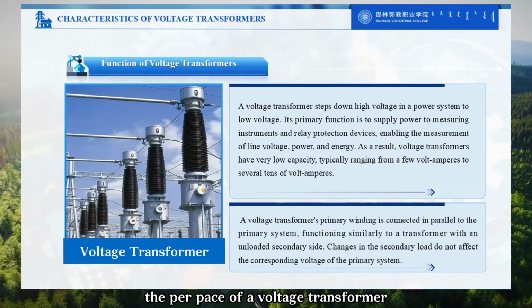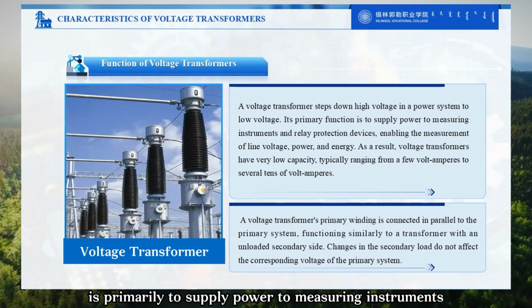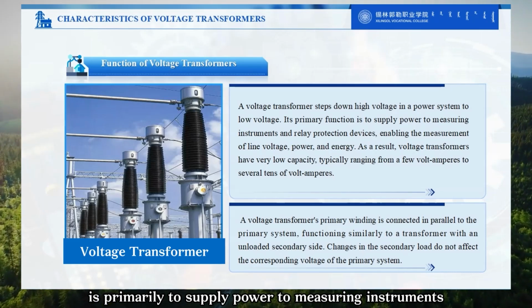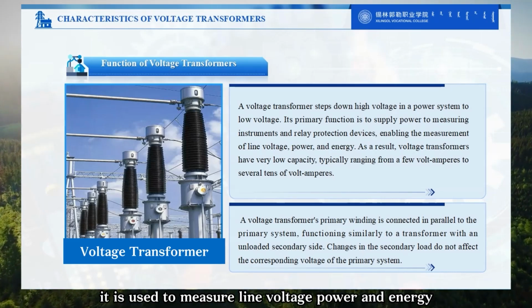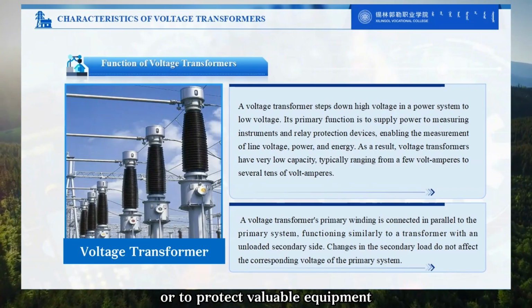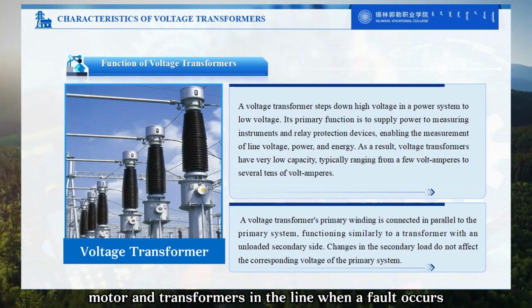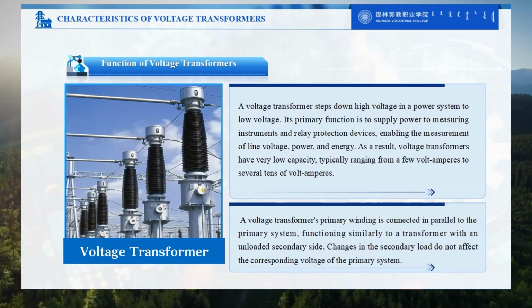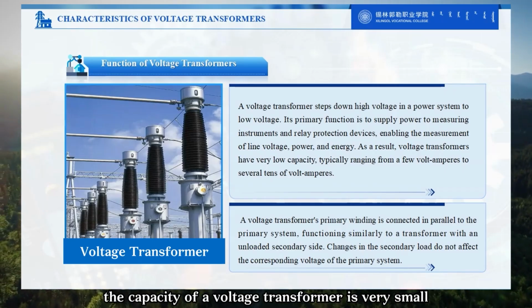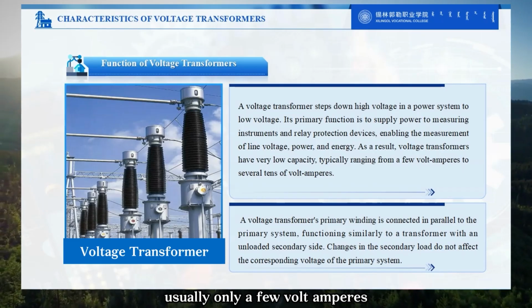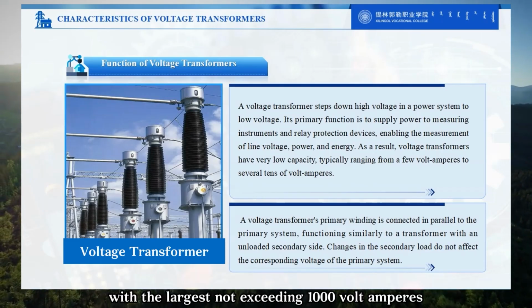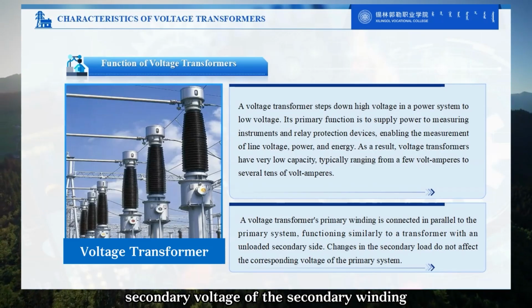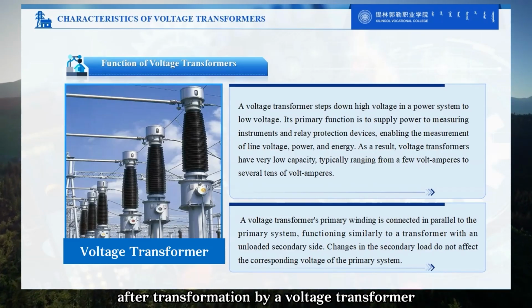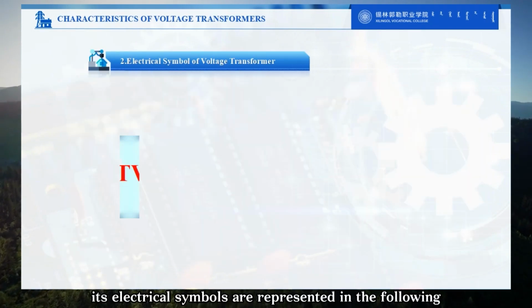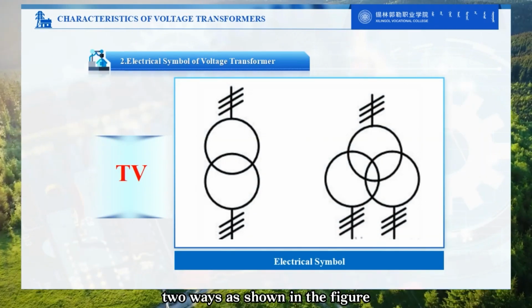The purpose of a voltage transformer changing voltage is primarily to supply power to measuring instruments and relay protection devices. It is used to measure line voltage, power and energy, or to protect valuable equipment, motors, and transformers in the line when a fault occurs. Therefore, the capacity of a voltage transformer is very small, usually only a few voltamperes or tens of voltamperes, with the largest not exceeding 1000 voltamperes. The standard rated secondary voltage of the secondary winding after transformation by a voltage transformer is 100 volts. Its electrical symbols are represented in the following two ways, as shown in the figure.